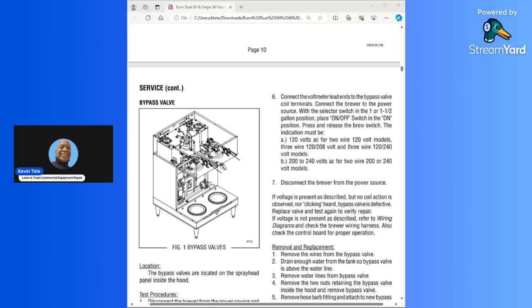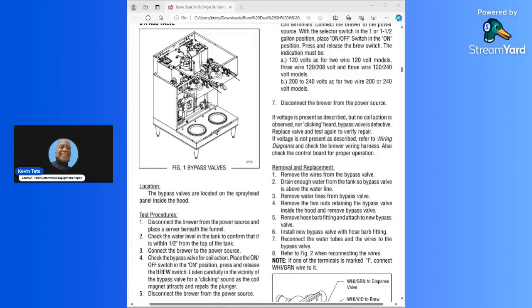The indication must be 120 volts AC for 2-wire 120 volt models, 3-wire 120/208 volt, and 3-wire 120/240 volt models. 200 or 240 volt AC for 2-wire 200 or 240 volt models. Disconnect the brewer from the power source. If the voltage is present as described, but no coil action is observed, nor clicking heard, the bypass valve is defective. Replace the valve and test again to verify repair. If voltage is not present as described, refer to wiring diagrams and check the brewer wiring harness. Also, check the control board for proper operation.